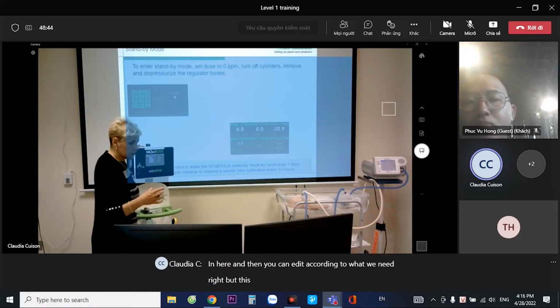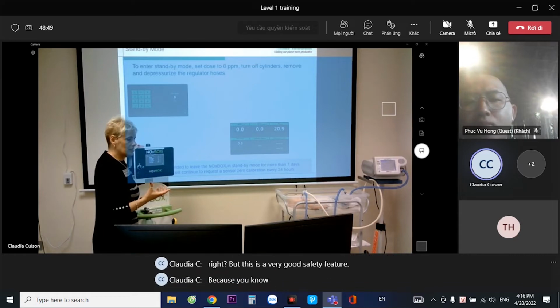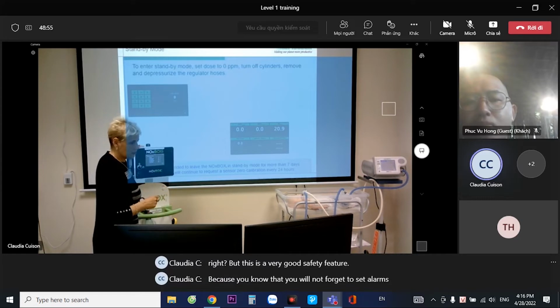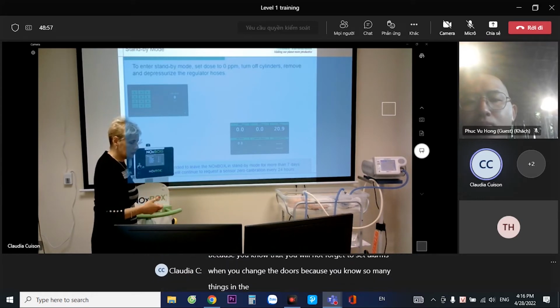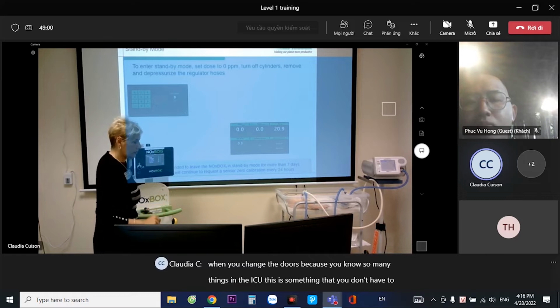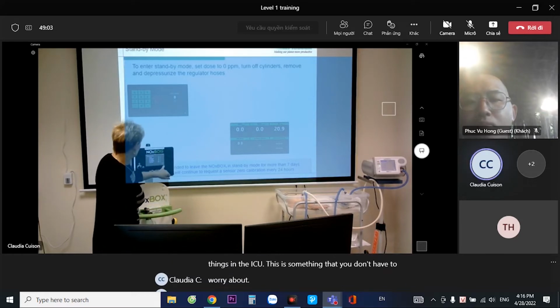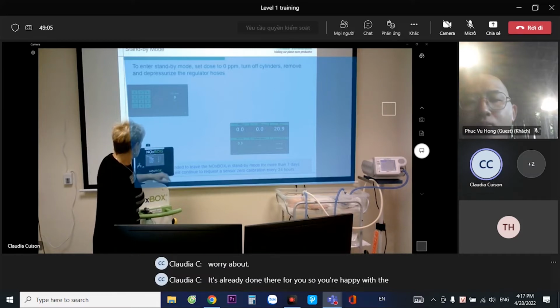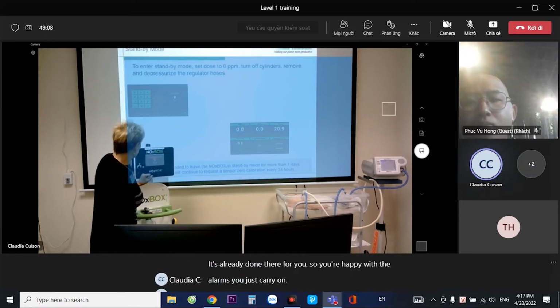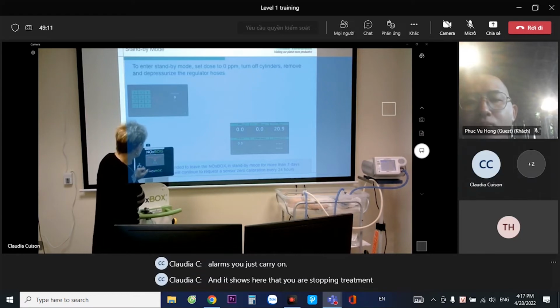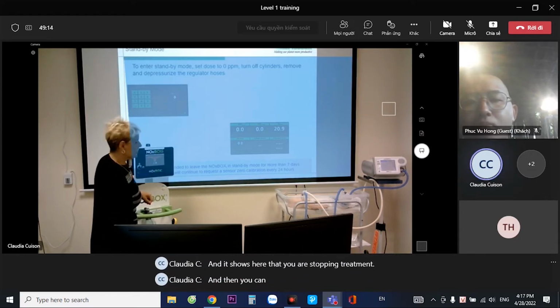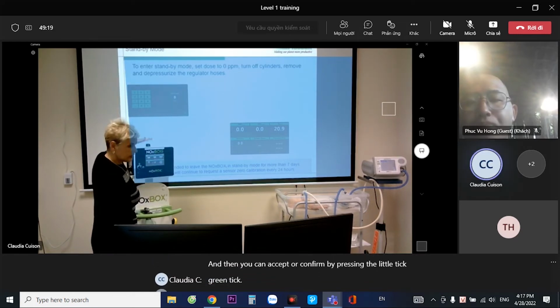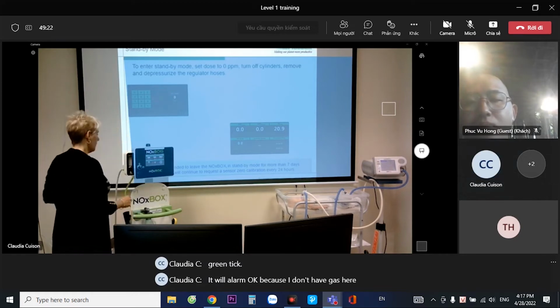But this is a very good safety feature because you know that you will not forget to set alarms when you change the dose, because you know so many things in the ICU. This is something that you don't have to worry about. It's already done there for you. So you're happy with the alarms, you just carry on. And it shows here that you are stopping treatment, and then you can accept or confirm by pressing the little green tick. It will alarm, okay, because I don't have gas here.